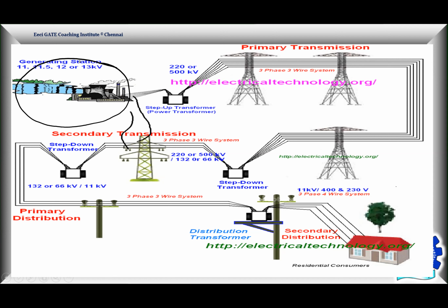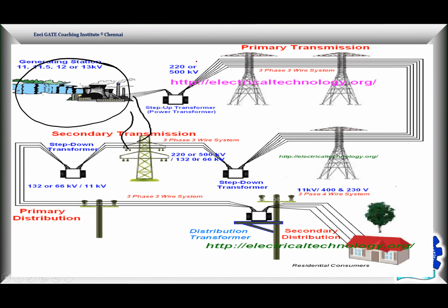So then the medium or secondary transmission comes into picture. Here in the picture, primary transmission is happening at 220 to 500 kV, and nowadays it can go up to 765 kV. After primary transmission, there is a step-down transformer stepping down from 220 or 500 kV to 132 or 66 kV. This transmission from here is called secondary transmission.